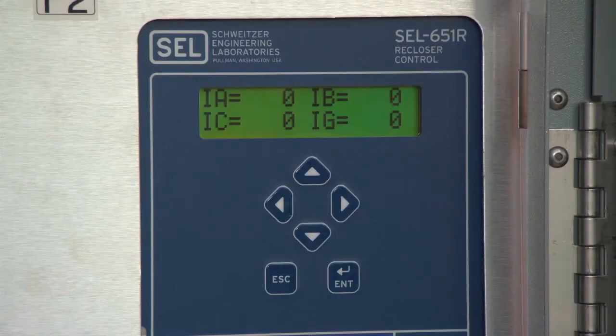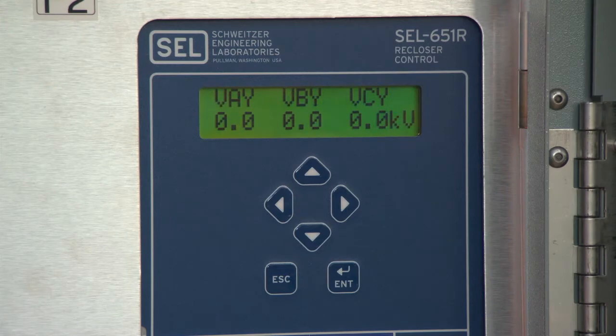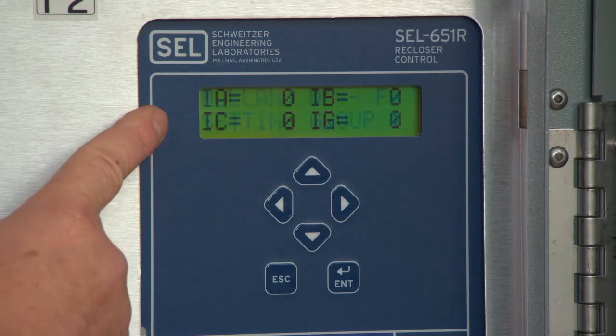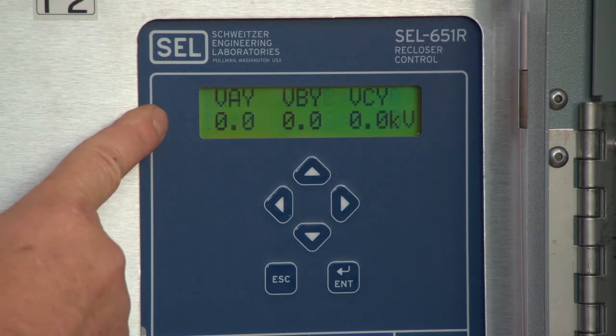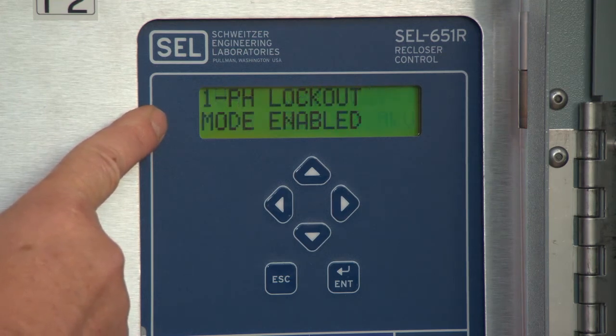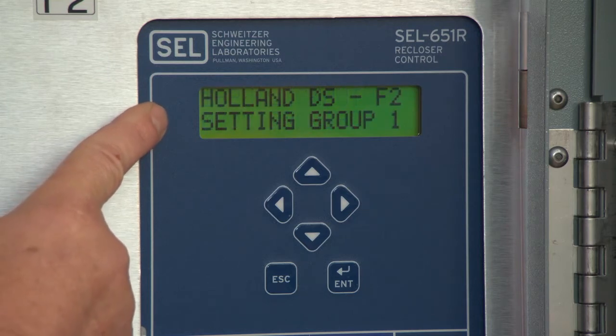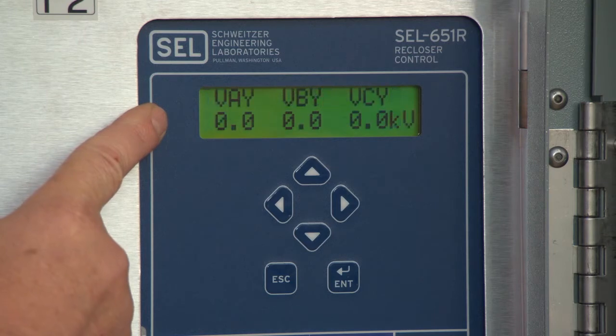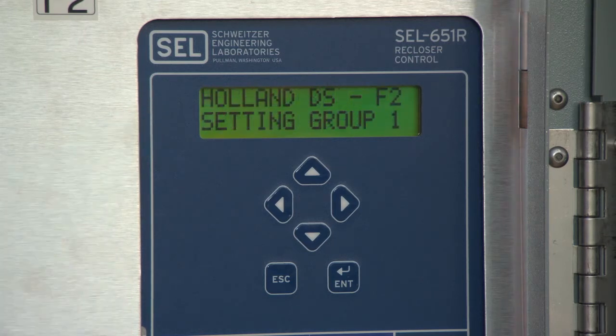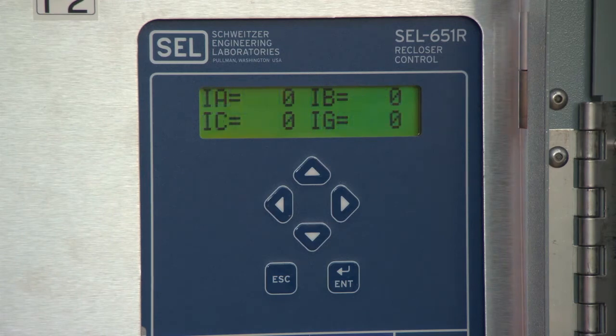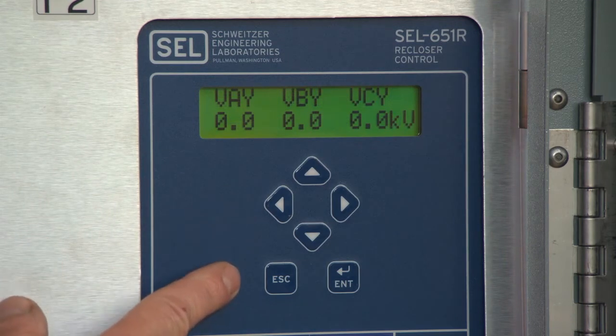The 651R controller display screen under normal conditions will scroll through various items such as the mode. In this case, single-phase lockout is enabled. The currents, the DS name, the setting group, the amperages, and finally, the voltages. Below the display screen are the arrow selector buttons and the enter and escape buttons.